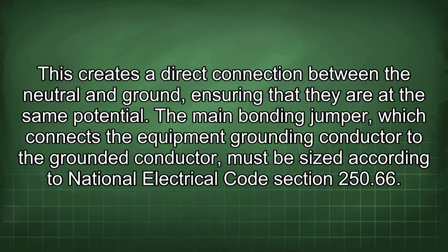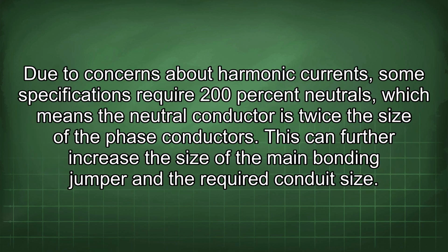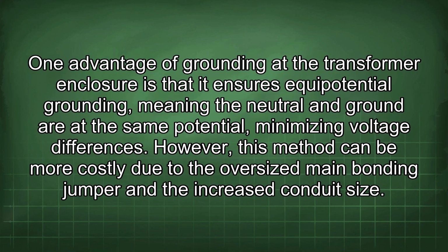The main bonding jumper, which connects the equipment grounding conductor to the grounded conductor, must be sized according to National Electrical Code Section 250.66. Due to concerns about harmonic currents, some specifications require 200% neutrals, which means the neutral conductor is twice the size of the phase conductors. This can further increase the size of the main bonding jumper and the required conduit size. One advantage of grounding at the transformer enclosure is that it ensures equipotential grounding, meaning the neutral and ground are at the same potential, minimizing voltage differences.